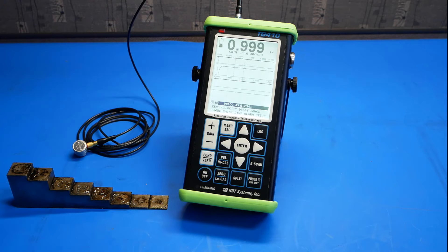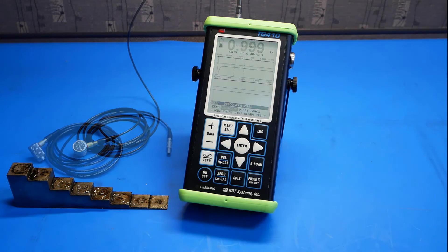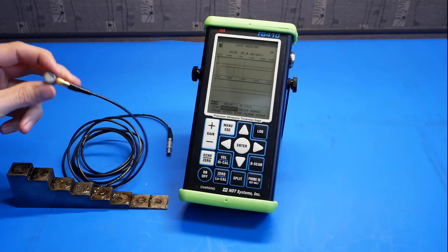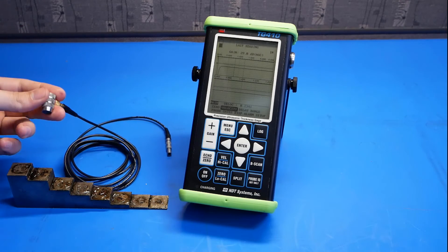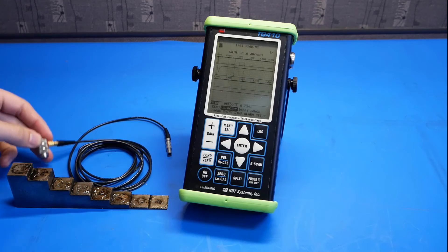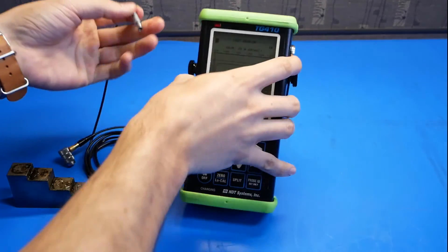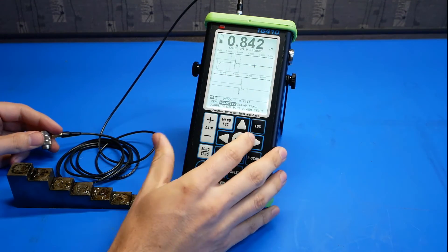Finally, let's look at the delay line transducer. Here we have a D11 delay line transducer. These are at 10 MHz. We'll plug the probe into the gauge as before, and we'll look for the setup.